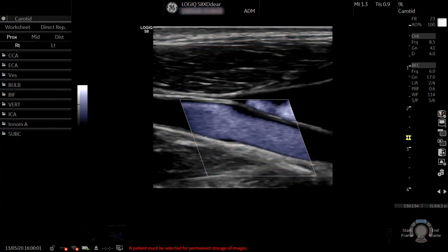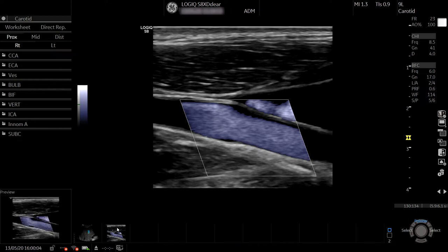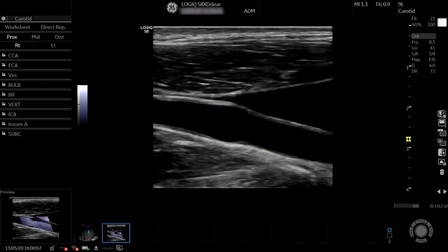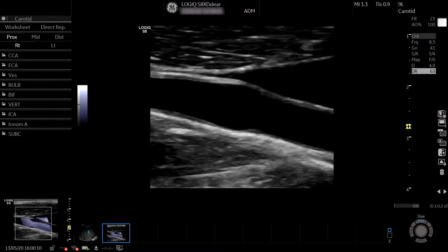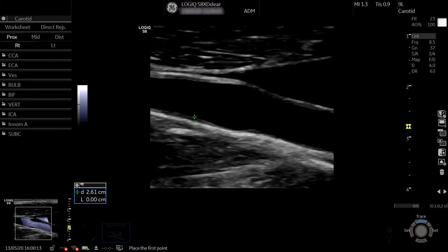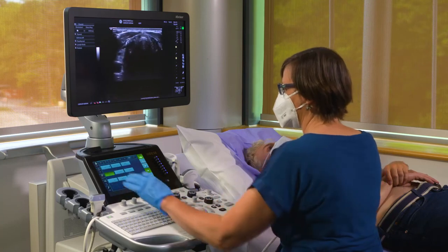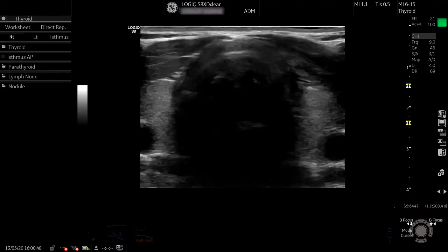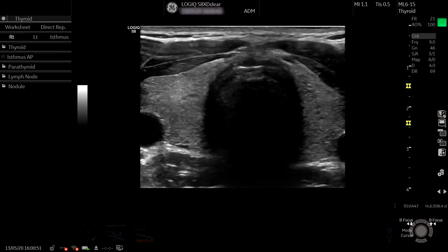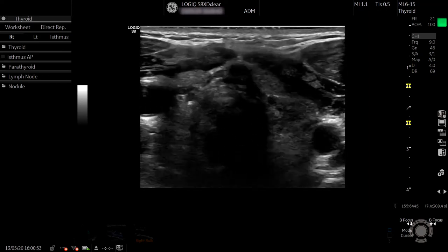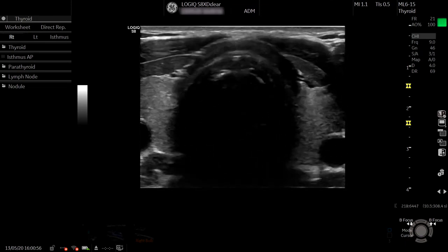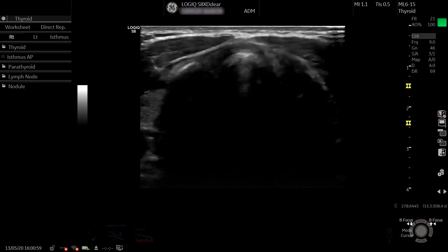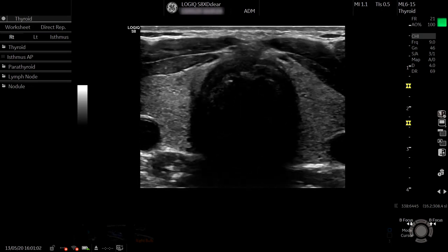Our raw data feature is across all our product portfolio, where we can bring up an archived image, remove the colour, manipulate the image, take a measurement, add a comment and resave. Let's now move to the ML6-15 and scan the thyroid gland. The ML6-15 is our high-frequency matrix array transducer with rows and columns of crystals, allowing us to focus in both the fundamental plane as well as the elevational plane, thus allowing near to far field resolution with no focal banding.